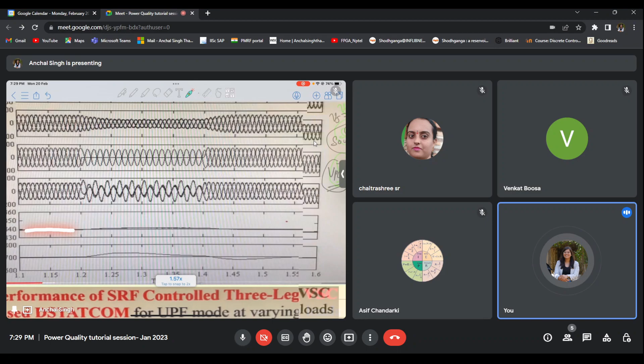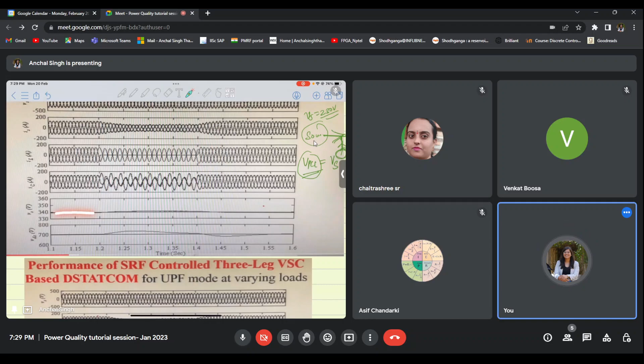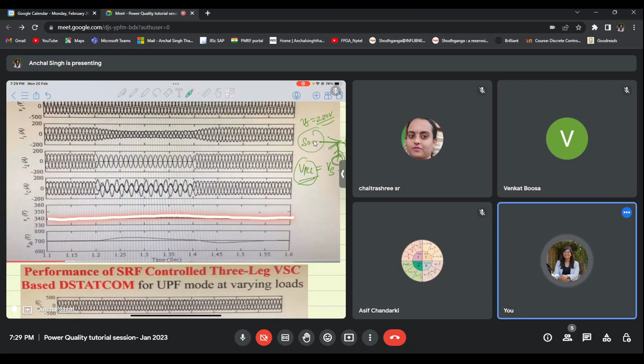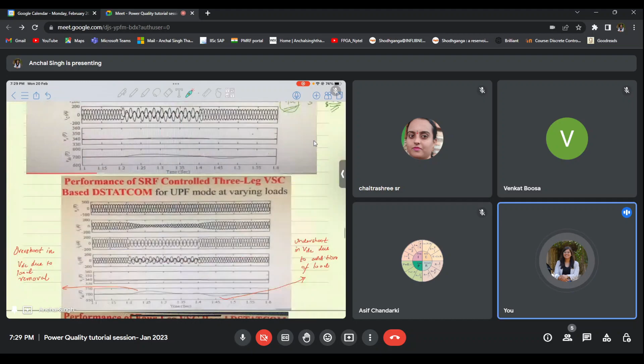And since I am operating in zero voltage regulation mode, you can see that Vs is very close to the reference. This actually should have been shown in a more colorful waveform, but this straight line gives me Vs peak, which is the voltage at which I want to regulate. Then there is a slight deviation because of the unbalanced load, and then it again came back to the Vs peak level. That means my system is perfectly tracking. Whereas in unity power factor mode, Vs is not perfectly tracking. Look, there is deviation, right? And here it is perfectly tracking. That means zero voltage regulation mode is properly working. So this is how you analyze the working of any system from its waveforms. Okay.